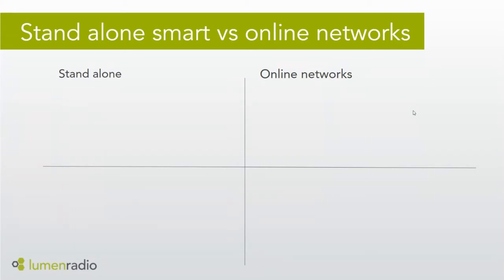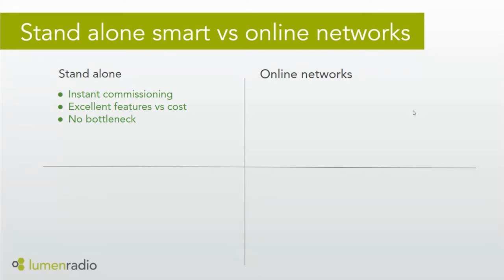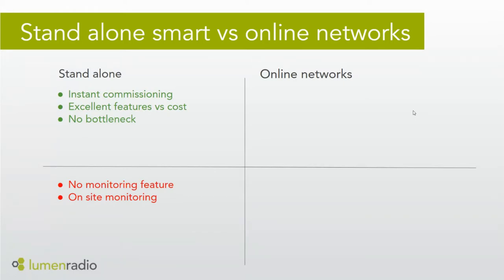So what's the difference between a standalone smart system and an online network? On a standalone system where luminaires talk to each other, you have instant commissioning, excellent features versus cost — all the smart abilities with programming, motion sensors, and manual control — but without the high cost of a gateway. There's no bottleneck, meaning if one luminaire is not functioning or there's maintenance nearby, the network keeps working. The disadvantage of a standalone network is there's no remote monitoring — only on-site monitoring, which can actually be a benefit if you are constantly on-site.